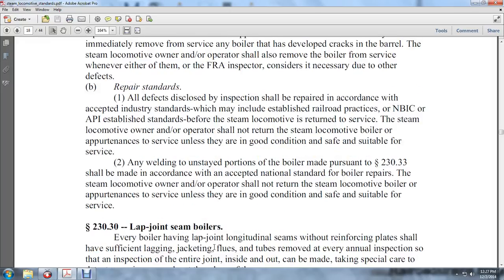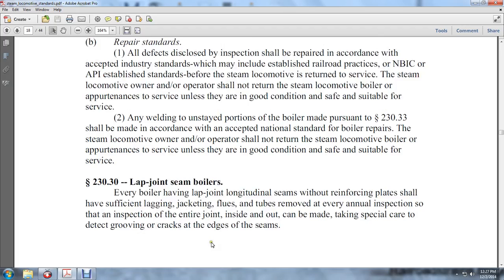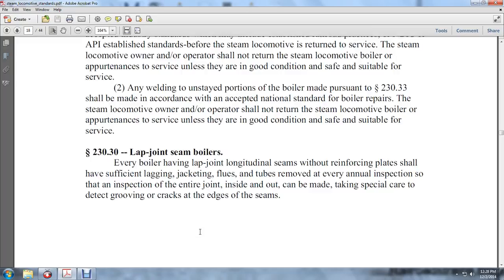Section 230.30 — Lap joint steam boilers: Every boiler having a lap joint longitudinal seam without a reinforcing plate shall have sufficient lagging, jacketing, flues, and tubes removed at every annual inspection — flues removed — for every annual inspection so that the inspection of the entire joint, inside and outside, can be made. Special care shall be taken to detect defects, grooving, and cracks in the edges of the seam.